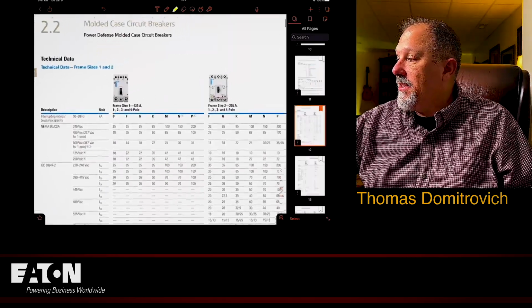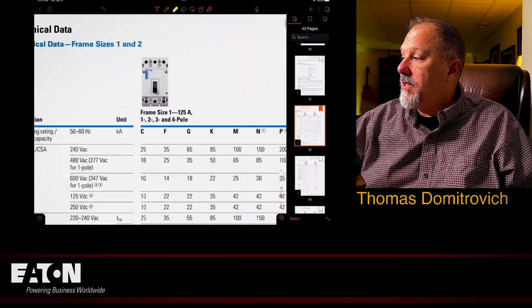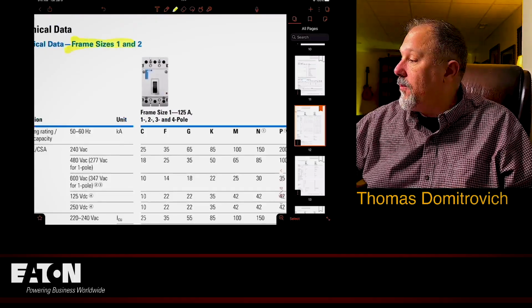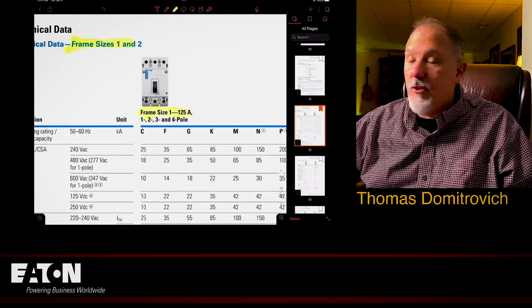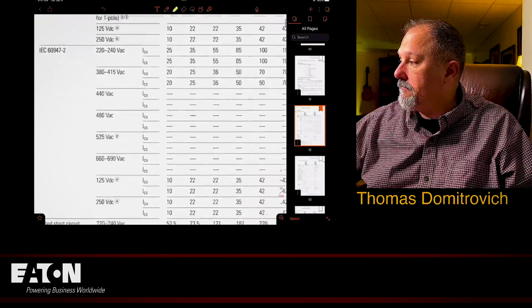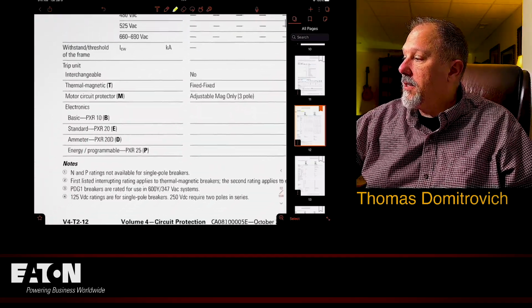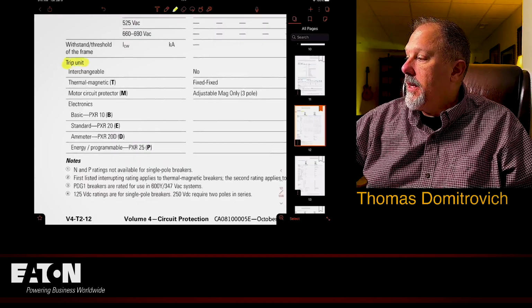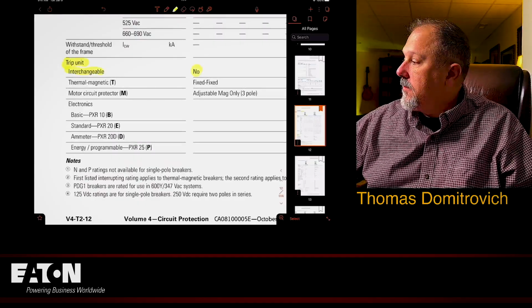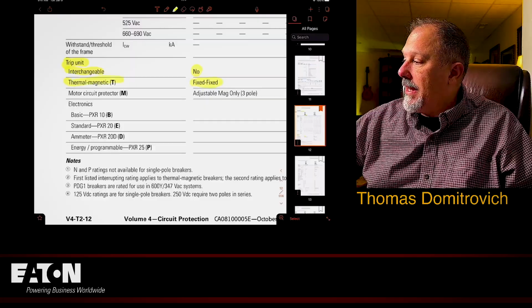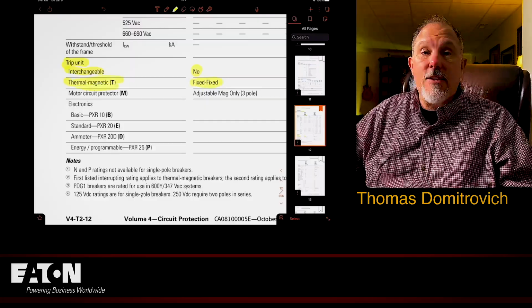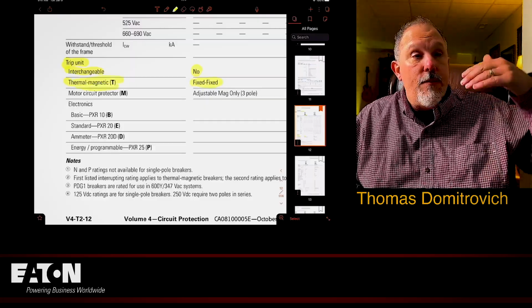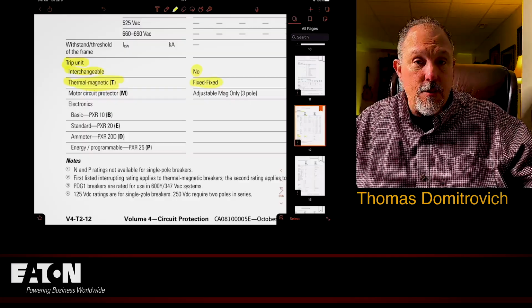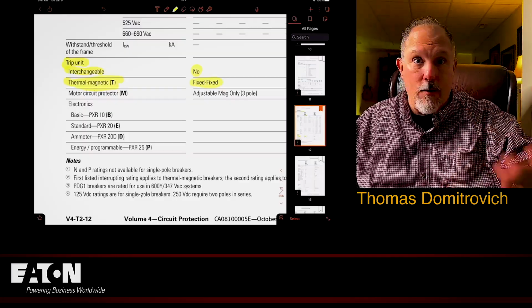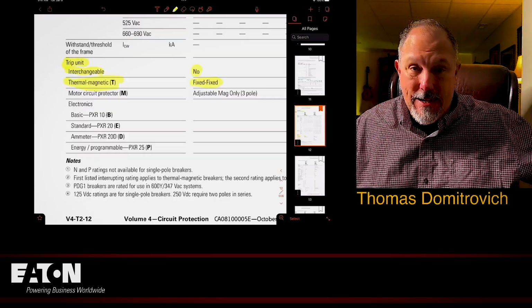All right, so where do I go next? The trip unit. So this is the technical data, frame sizes 1 and 2. So we know what 1 and 2 is. Frame size 1 goes up to 125 amps. And we're gonna look for the trip unit. It's not interchangeable. It's fixed. Thermomagnetic is fixed. And that's what I was telling you earlier. Remember, some of these circuit breakers, thermomagnetic circuit breakers, it is what it was, what it shall be, and it will never be anything different.